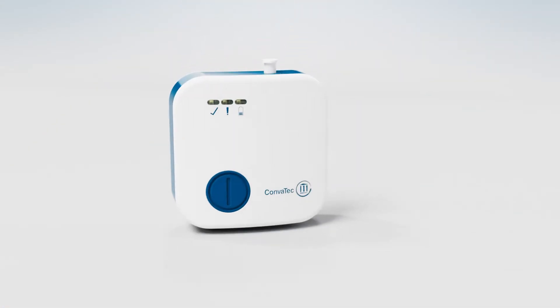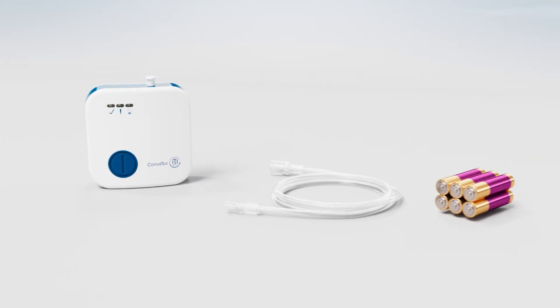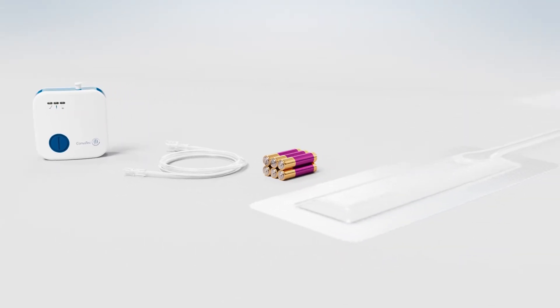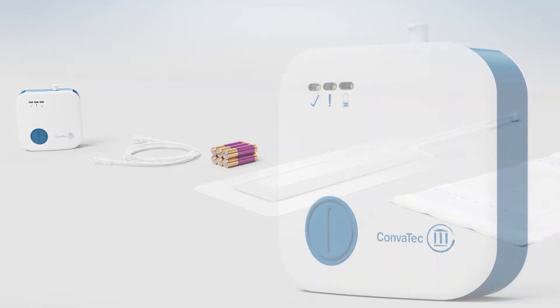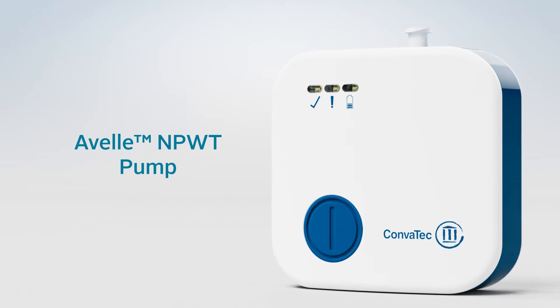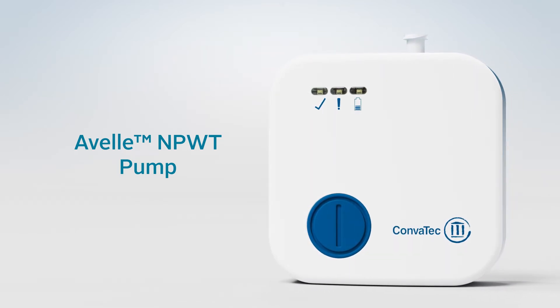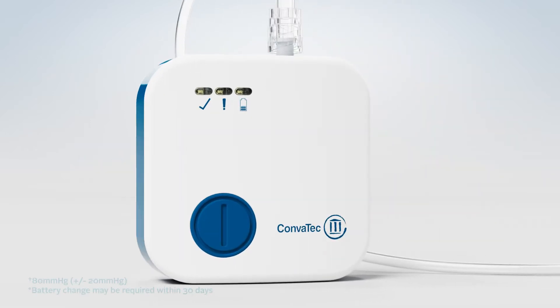The Avelle system consists of a non-sterile, single-use pump, supplied with tubing and two sets of lithium AAA batteries. Avelle dressing packs include a Hydrofibre Technology negative pressure wound dressing and six fixation strips. The Avelle pump is small, portable and powered by lithium batteries, which enables up to 30 days of therapy and delivers 80 mmHg of mercury negative pressure therapy to the wound bed.